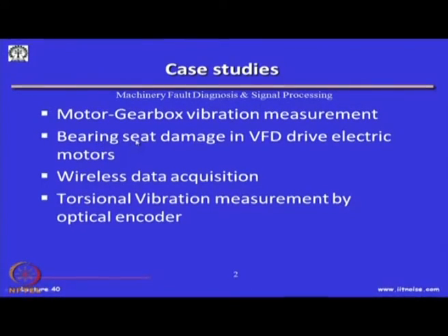Another case study would be the bearing seat damage in VFD drive electric motors, which I had briefly mentioned while talking about motor current signature analysis. A new area coming up in condition monitoring is wireless data acquisition. When we have a machine with transducers mounted, cables have to be drawn to the data acquisition unit and then computer-based systems do the analysis. Many times it becomes cumbersome to have a lot of cables coming from different sensors in the plant. People are exploring wireless data acquisition, but earlier I mentioned how bandwidth limitation limits us in terms of what data rates we can acquire from a machine, and how that hampers meaningful analysis of dynamic signals through wireless data acquisition.